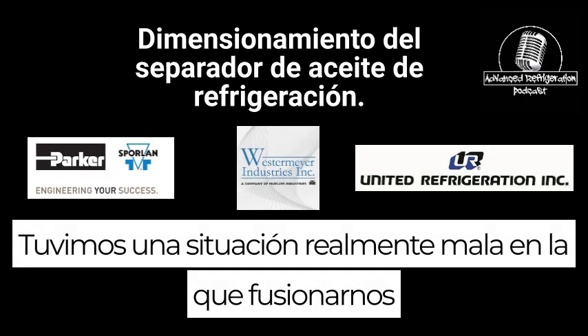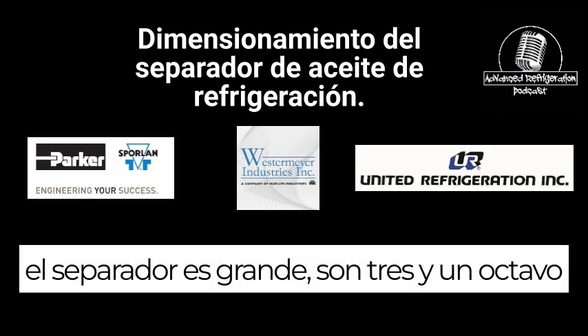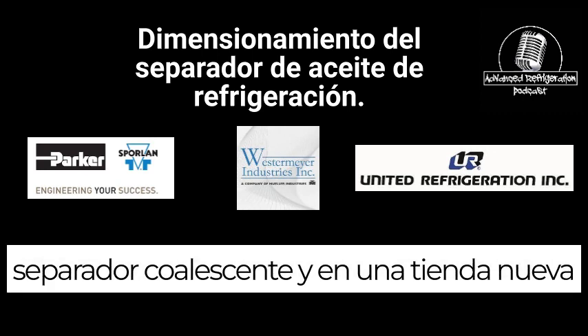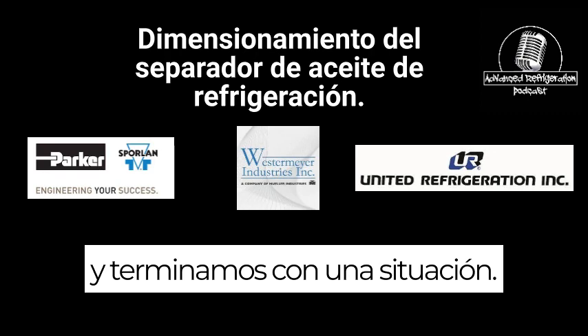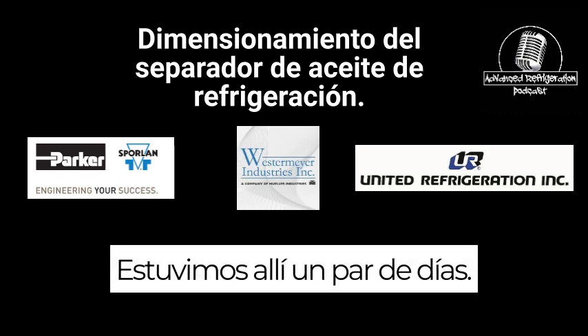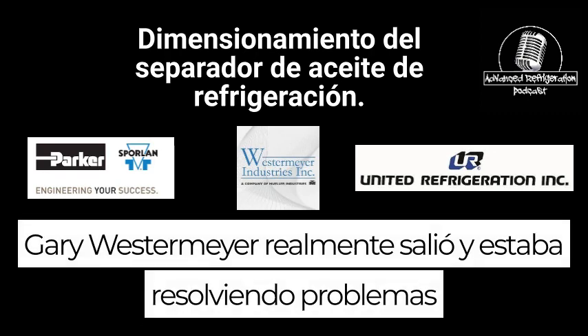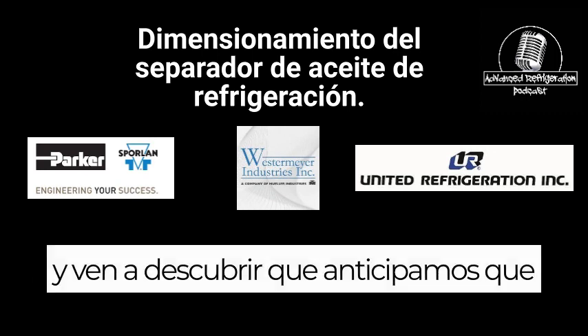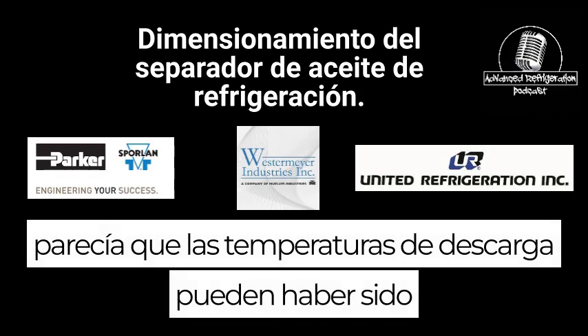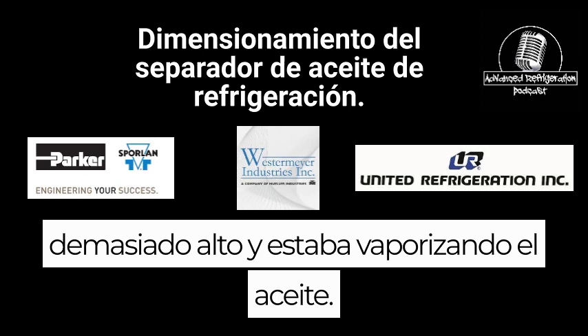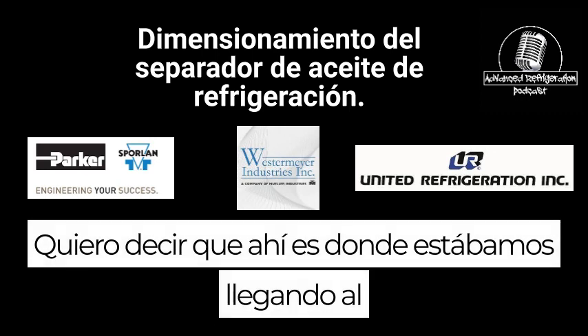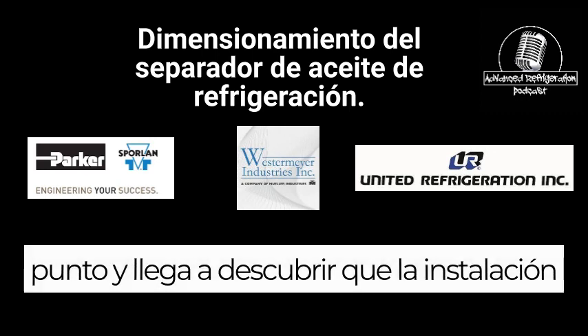We had a really bad situation with a coalescing separator. It's a big one, a 3 1/8 coalescing separator, on a brand new store. We were out there for a couple of days. Gary Westermeyer actually went out and was troubleshooting it. We anticipated that the discharge temperatures may have been way too high and it was vaporizing the oil.